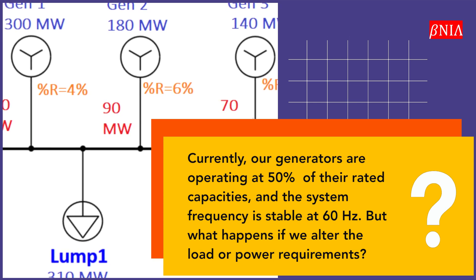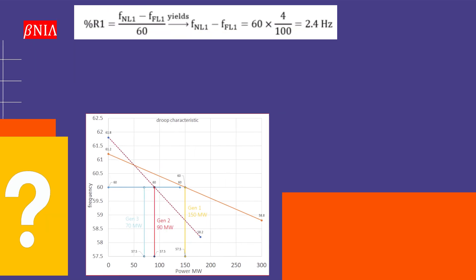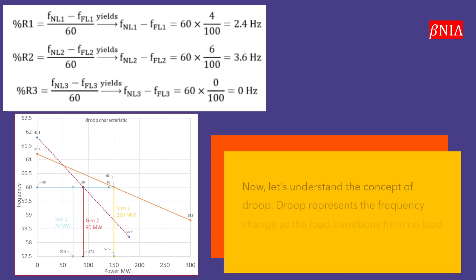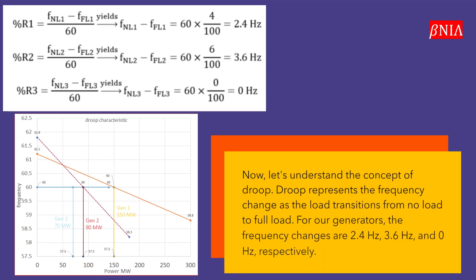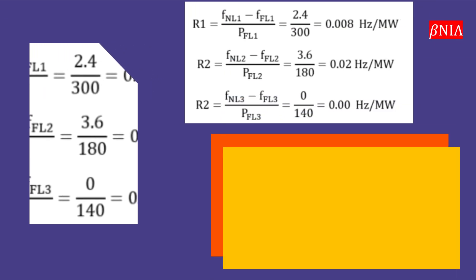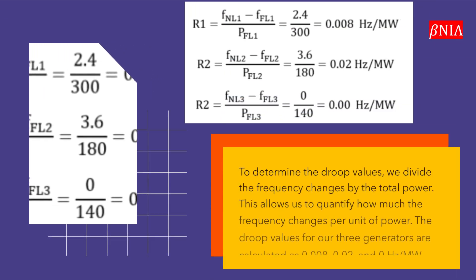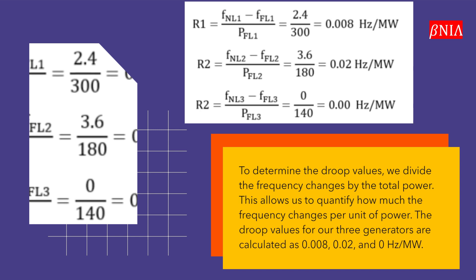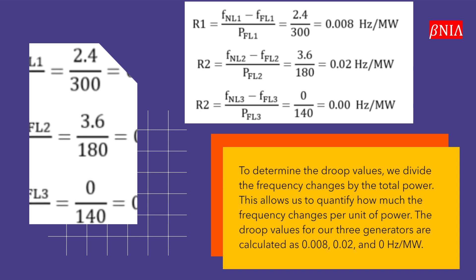But what happens if we alter the load or power requirements? Let's understand the concept of droop. Droop represents the frequency change as the load transitions from no load to full load. For our generators, the frequency changes are 2.4 Hz, 3.6 Hz, and 0 Hz, respectively. To determine the droop values, we divide the frequency changes by the total power. This allows us to quantify how much the frequency changes per unit of power.